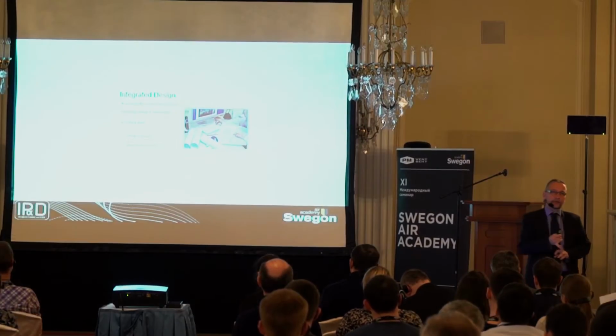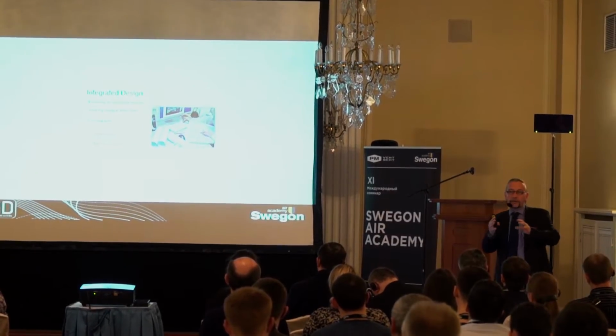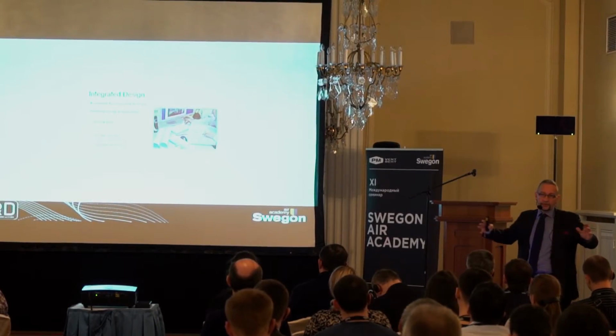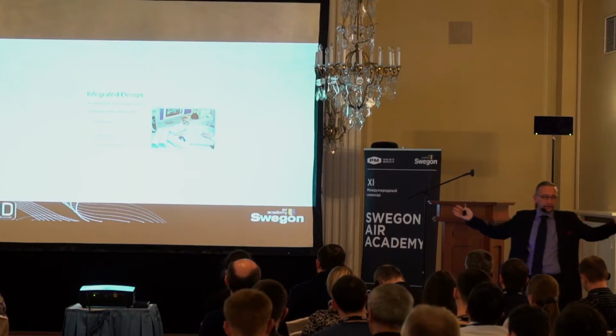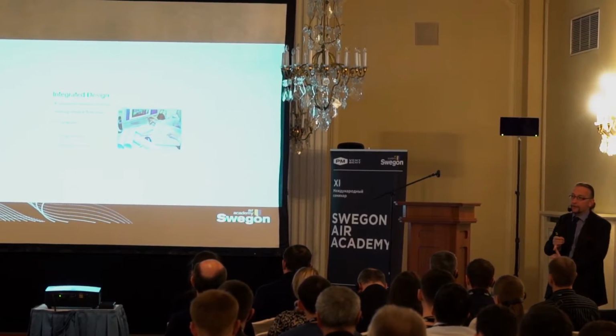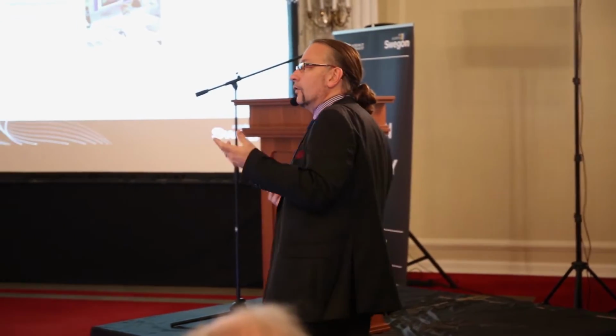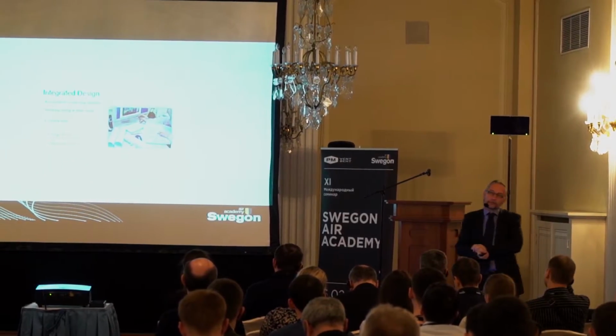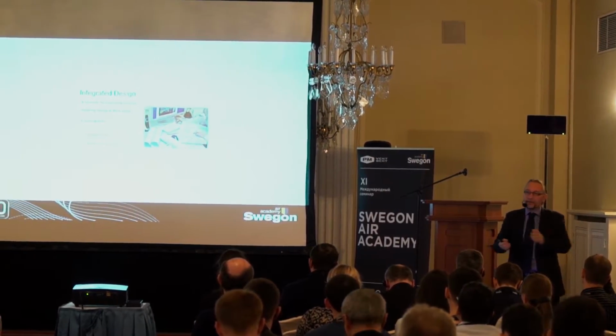I know that in a lot of buildings, you might want to overpressurize because you don't trust the building to be airtight. What happens then is all the energy you put into the air or water gets pressed out of the building. If you have 10% overpressure, you're putting 10% cooling or heating outside, not into the building. On top of that, you press moisture into the construction, helping fungus and mold grow. One hotel group had to refurbish over 5,000 hotel rooms because they were running on overpressure. Imagine standing in the shower producing humidity that then gets pressed into the walls—it becomes a very smelly situation after a couple of years, and quite unhealthy too.